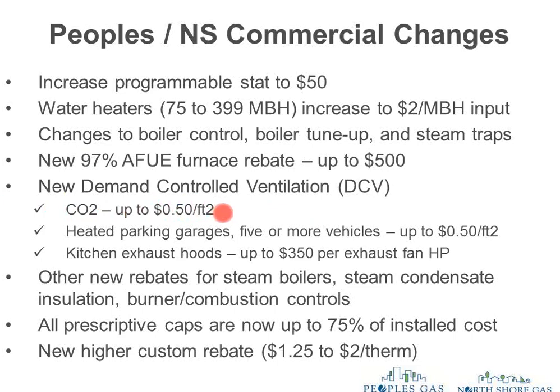You can't get more than you pay for the product, obviously. So if it costs you X amount of dollars to install it, and the rebate calculates higher than that, you can't get the higher amounts. You're limited there. You can only get, I believe, don't quote me, but I believe it's 75% is the maximum you could get. So if you paid $1,000 to install a DCV system, the most you could get would be a $750 rebate, I believe. In addition to CO2 sensors for space control, and by the way, if you need more information on demand control ventilation CO2 sensors, we did do a webinar on that a few months ago, and it was recorded. So send me a note, and I'll give you the link to that and where you could watch it and see how these systems all work.